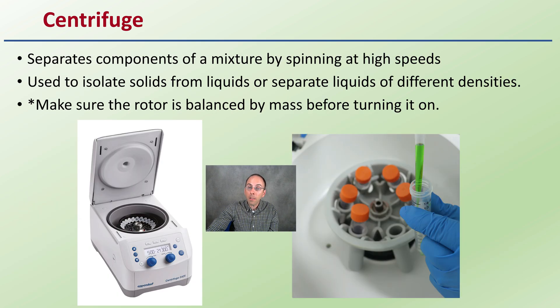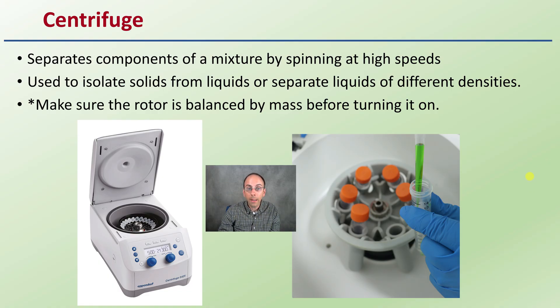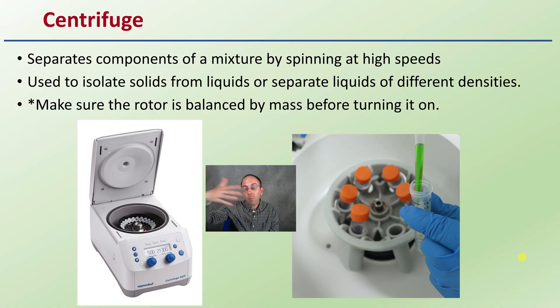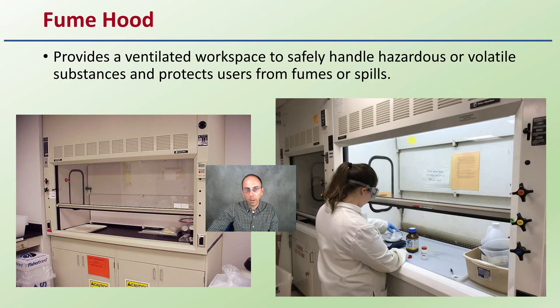The centrifuge spins really quickly at high speeds and is used for separating out liquids of different densities. You can decant the top liquid. When utilizing these, make sure the rotor is balanced based on mass — if it's unbalanced, it will vibrate off the table and cause all sorts of issues, not to mention loss of the experiment and spilling of chemicals.